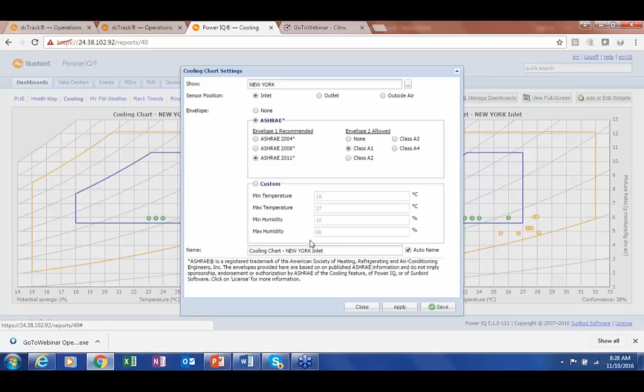The data can be exported for analysis, and we provide easy metrics that help you understand your conformance index, meaning out of all my cabinets, how many are in conformance with ASHRAE's recommended range, and how much energy I could potentially save. Clearly I have some cabinets that are too hot, so I have a cooling problem, and we'd rather you address that first before trying to save energy. This gives you an at-a-moment view of how your environment is in terms of cooling.